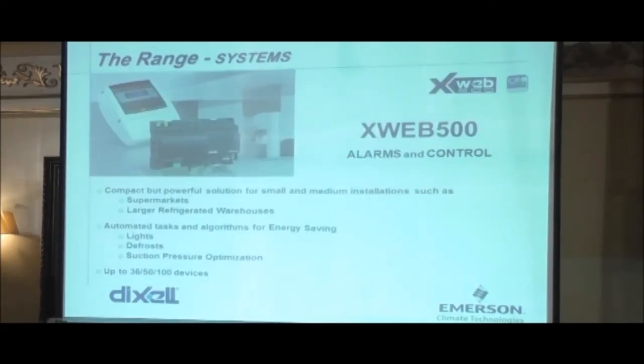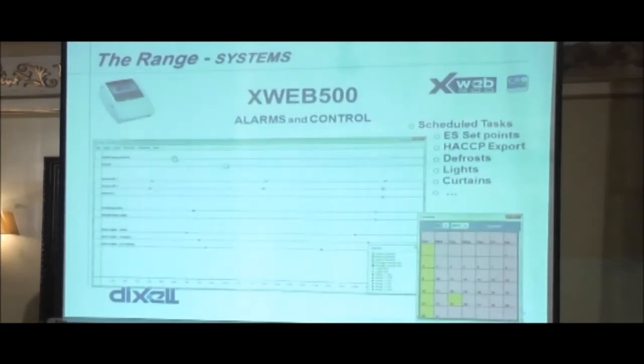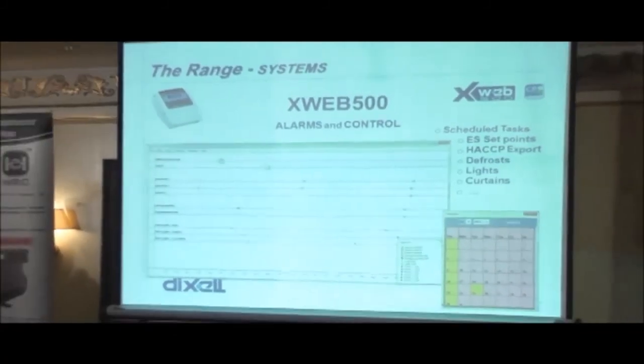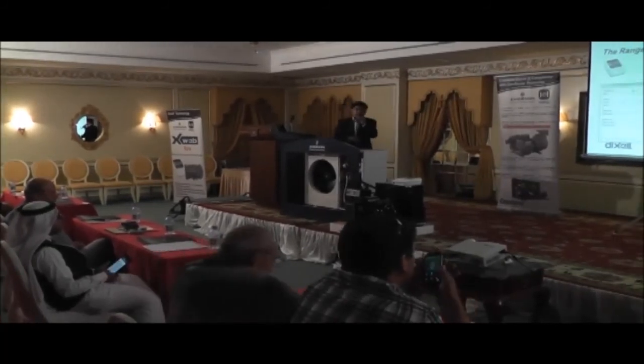XWeb 500 is similar to the XWeb 300 principle, but with an added function of controlling each instrument. For example, this is what we call the scheduler. You can set each instrument when to defrost, when to switch on and switch off the light, when to switch on and activate the energy saving management of the system. And for example, if you know the schedule of some holidays, you can also include that holiday schedule using the calendar function. So, for example, there will be no store operation. You can increase the set point and you can switch on the energy saving at an earlier time.